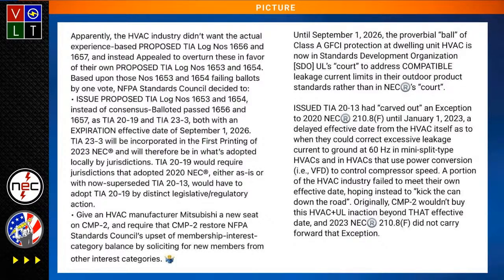The reason they don't like that, and I kind of agree a little bit, is there has to be a way to lock it into that 20 milliamp setting, because you could turn it back up to 50, or turn it back up to 100, or change it. So that's the kind of thing I see where they're coming from. But the reason they're mad is because you can use a GFPE device, dial it down to 20, and pass code. And to me, I think that's fine.